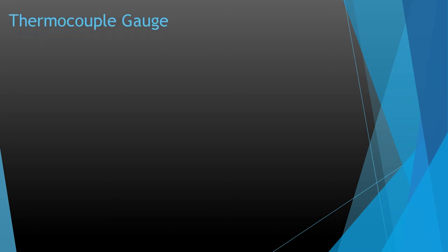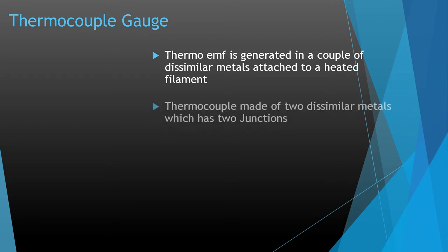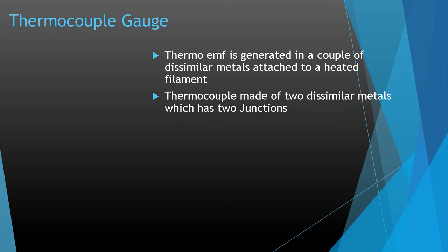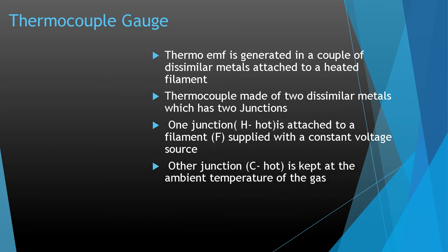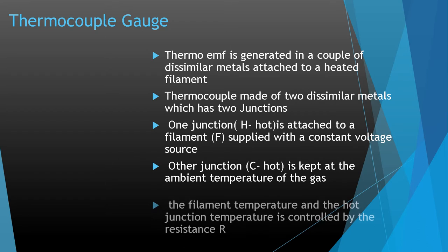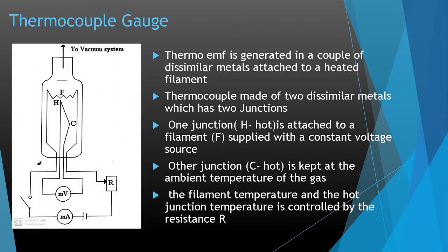The next type is the thermocouple gauge. A thermoEMF is generated in a couple of dissimilar metals attached to a heated filament. The thermocouple of dissimilar metals has two junctions. One junction, H (hot), is attached to a filament supplied with a constant voltage source. The other junction, C, is kept at the ambient temperature of the gas. The filament temperature and the hot junction temperature are controlled by a resistance R. In the schematic diagram, H represents the hot junction, F represents the filament, C represents the cold junction, and R represents the resistance.